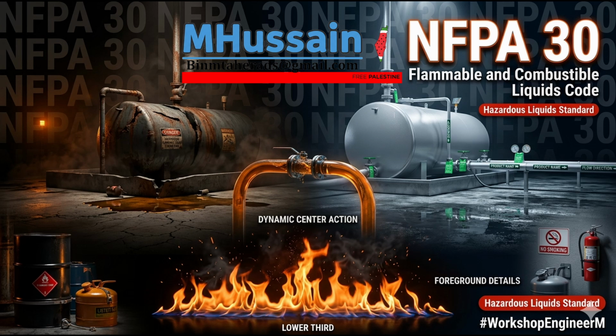Which means if you have a massive pool fire of a non-miscible hydrocarbon spreading across your warehouse floor, and your suppression system drops 0.60 GPM of pure water on it, the burning fuel just floats on top of the rapidly accumulating water. Exactly. You essentially build a boat for the fire. The sprinkler system creates a rushing current of water that carries this burning hydrocarbon right out the loading dock doors, down the drainage trenches, and spreads the fire into totally new sections of the building. You create a flaming river.